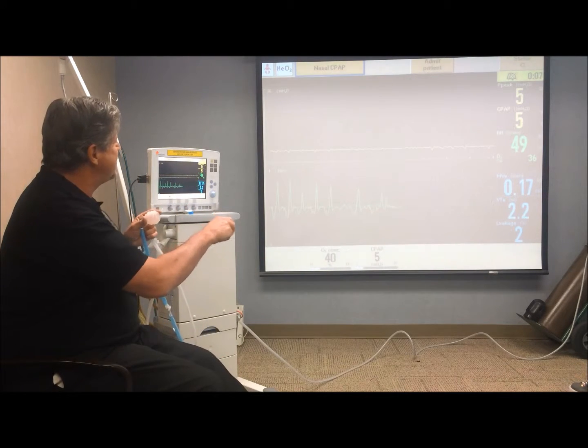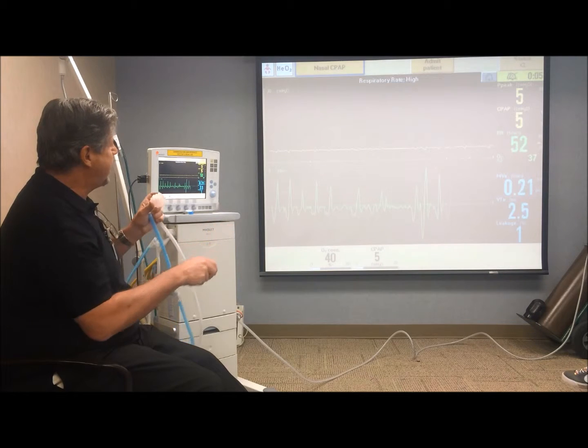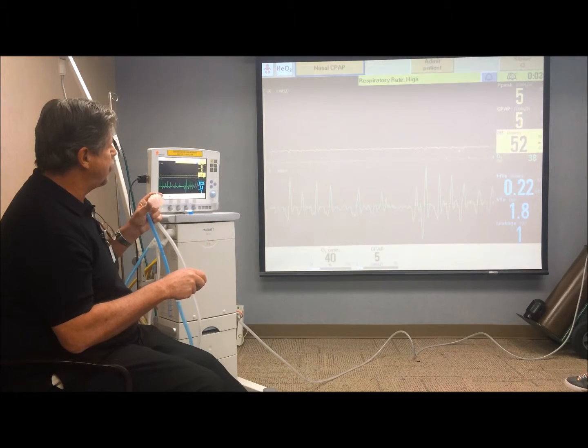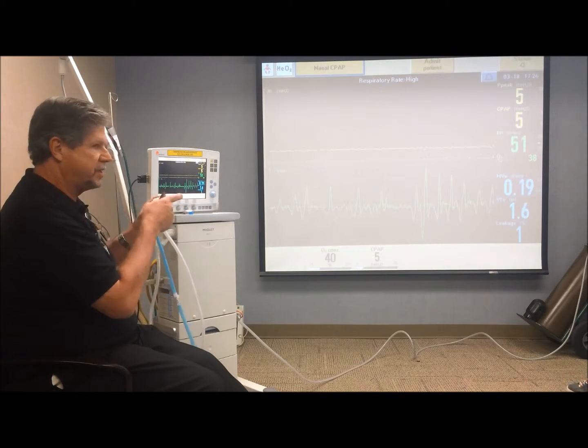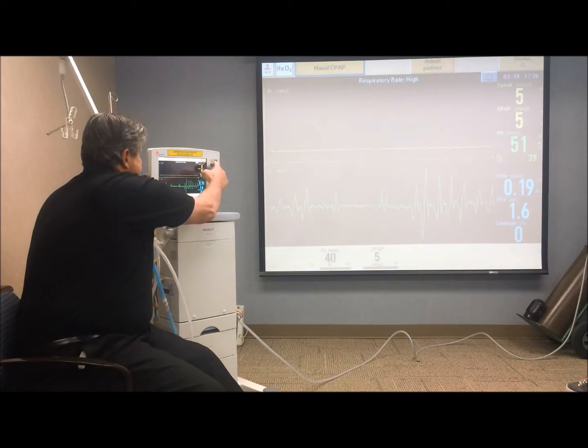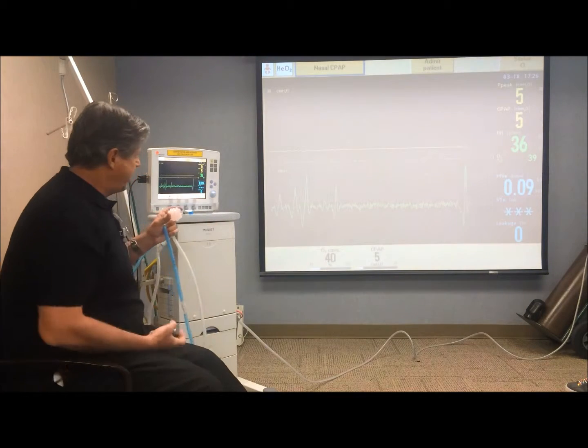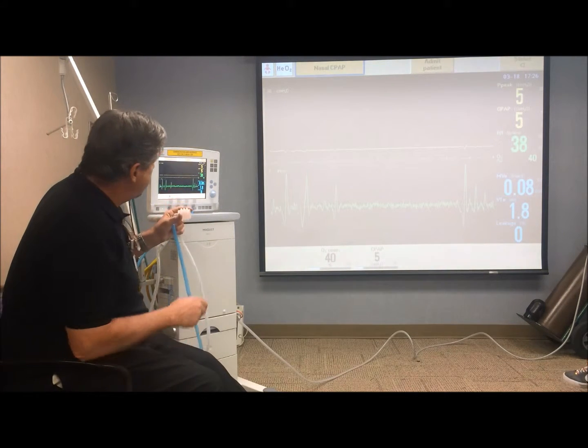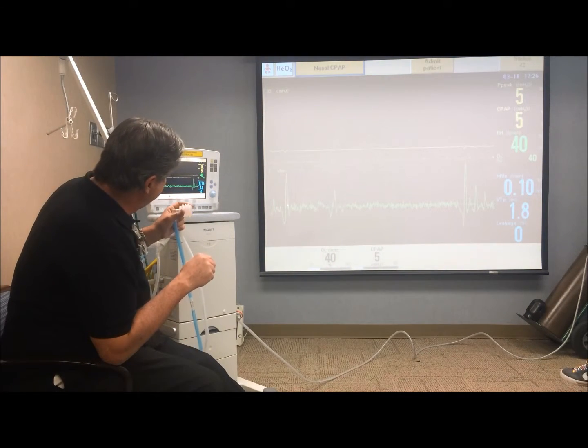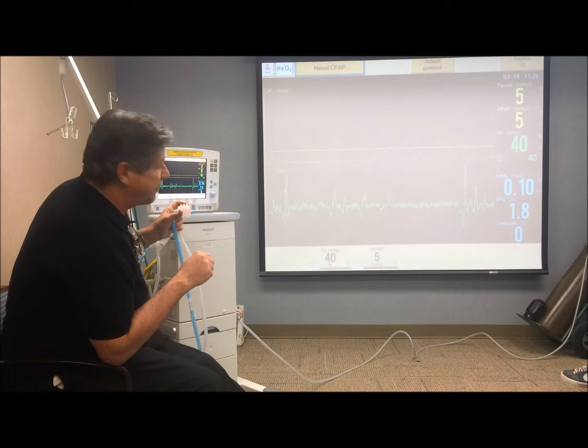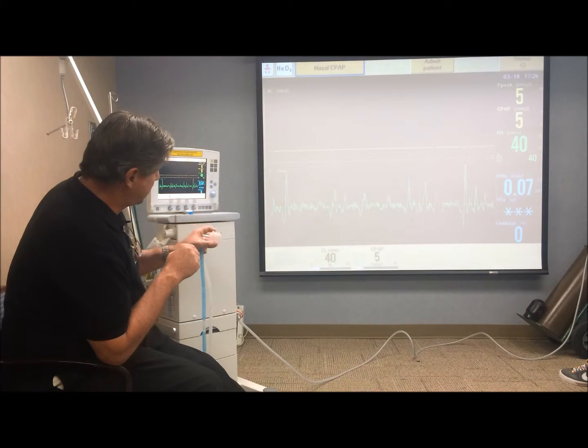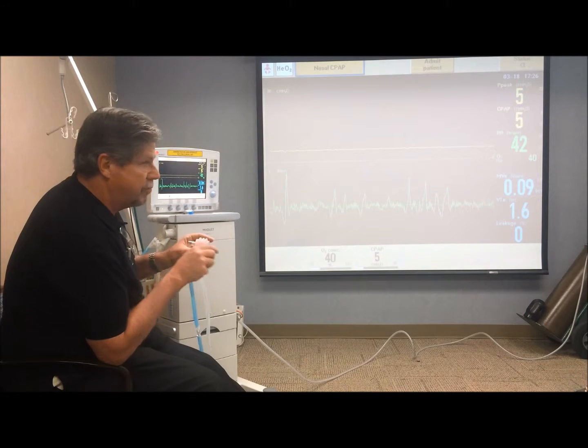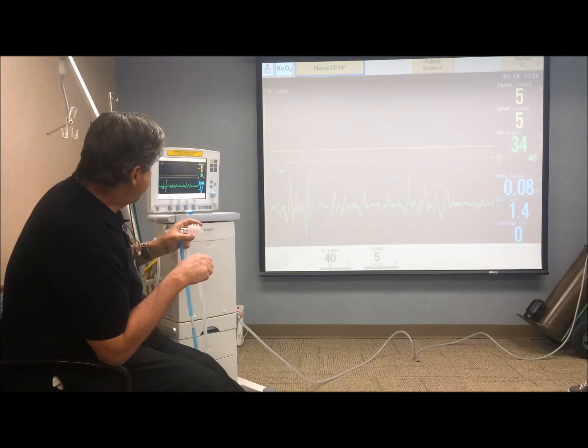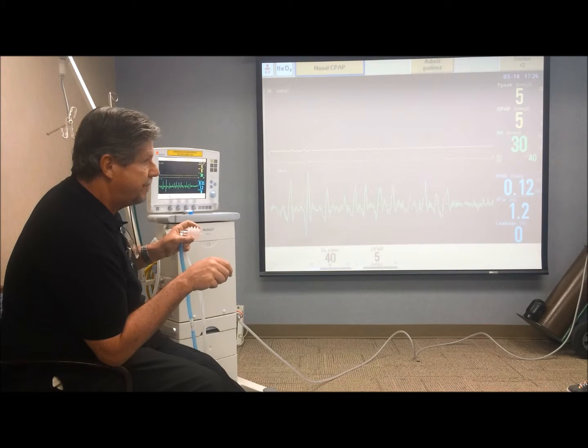So we have a CPAP level, and every time I move the lung, we see a little movement and pressure going down and then up again because of the movement. You can see that I'm just flicking the lung, but I'm creating enough movement so the ventilator can measure this flow change of what's occurring as a result of the test lung moving in and out. And that's what the ventilator uses to count the rate.